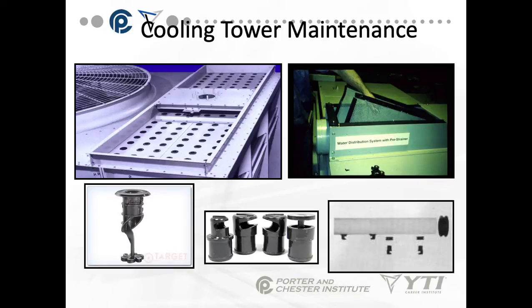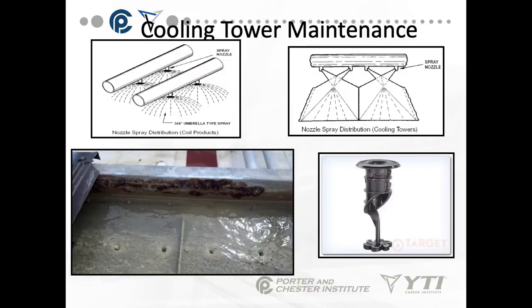So along with cooling tower maintenance comes inspection of all the parts, pulling the filters. Okay, you see top right is what the pre-strainers are. And the spray heads are here down on the bottom. Those need to be cleaned out because they get gunked up after a while. Okay, then you remove the nozzles, you inspect the chambers, you clean out any of the holes and fittings that are in here. The spray heads need to be cleaned so that they maintain proper operation.